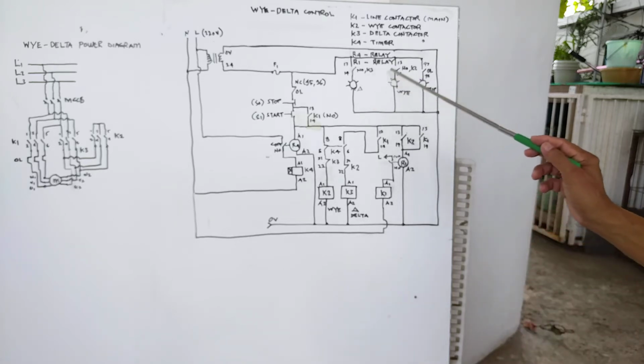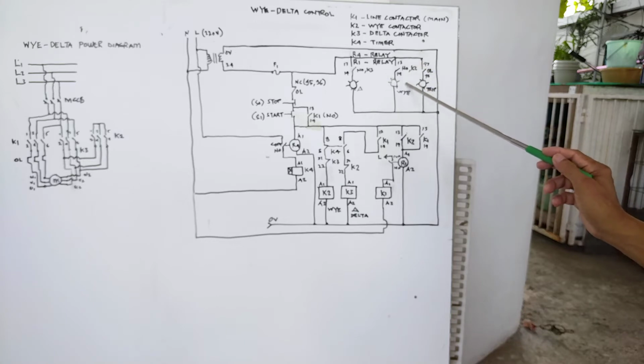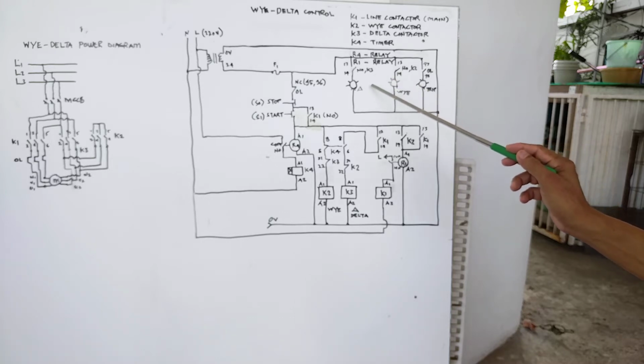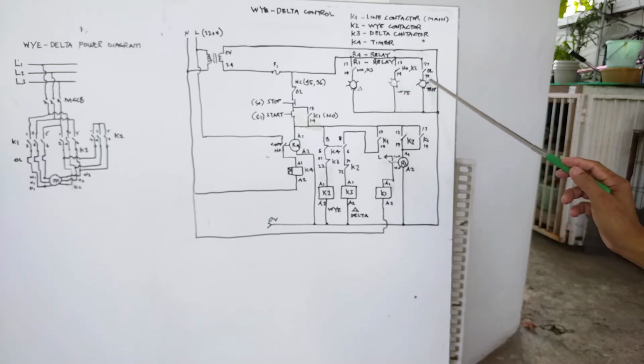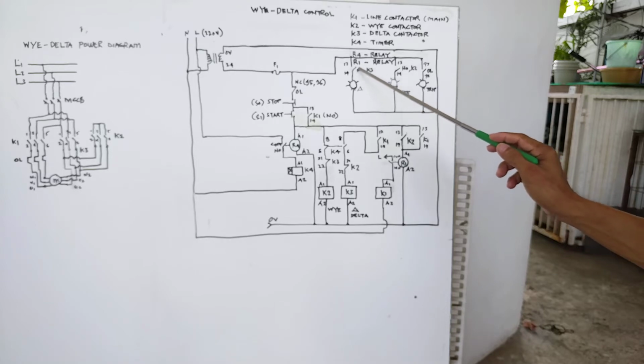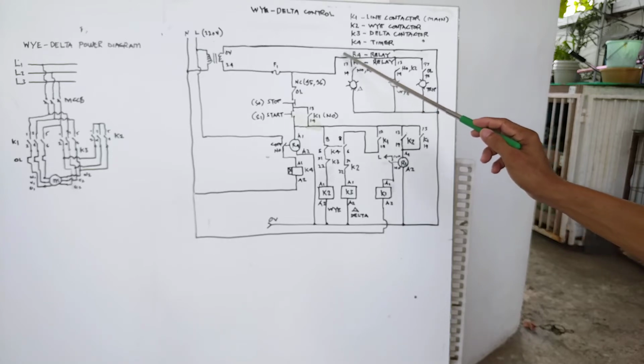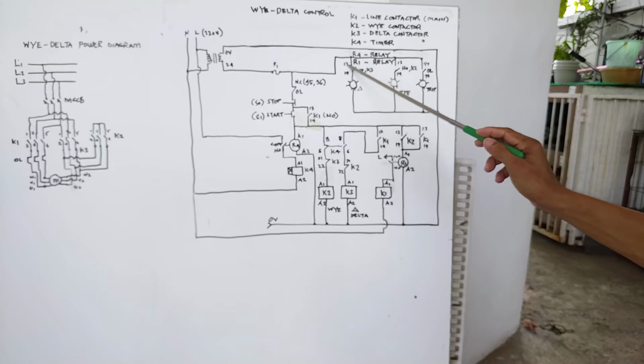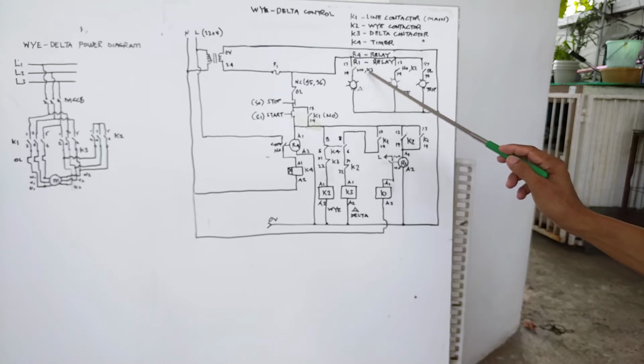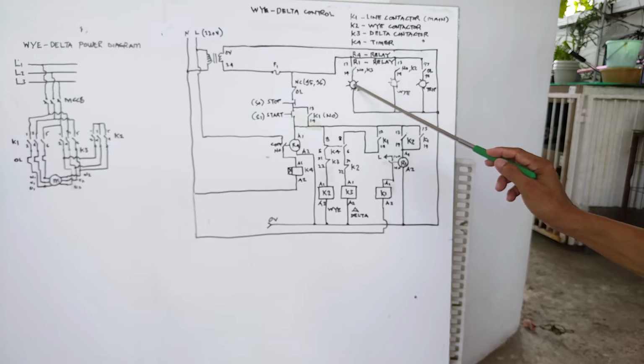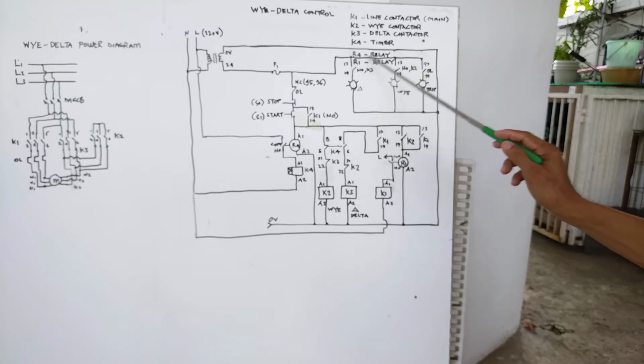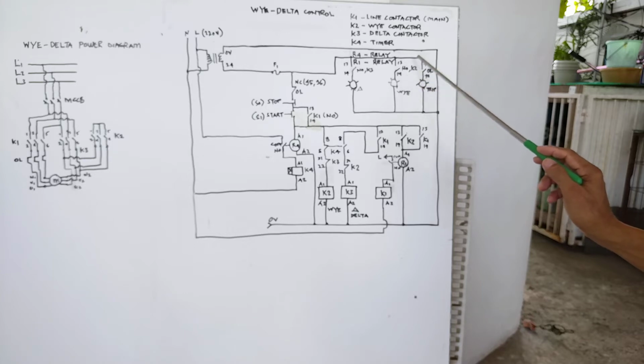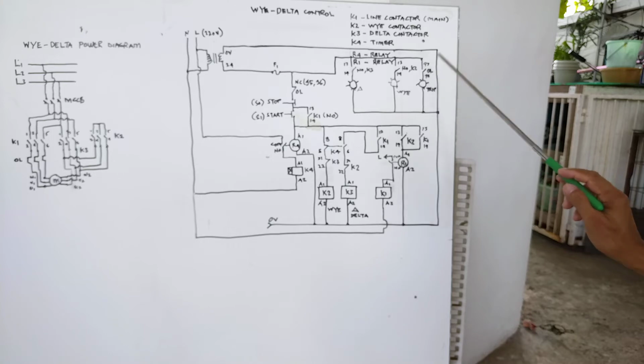So there is a Y indication lamp when it is running at Y, then a delta lamp when it is running at delta, then we have our trip. Now we are getting our delta using the normally open contact. So 24 volts will go to terminal 13 of the normally open contact of K3, then to the indication lamp. Likewise, this one also uses the normally open contact of the K2 Y contactor. Then the trip will, of course, come from the overload relay. So let's trace it.